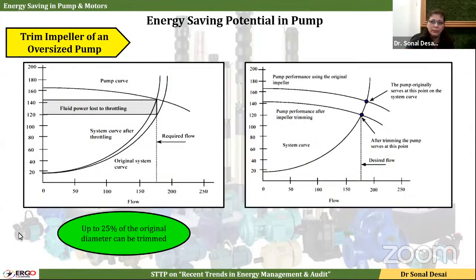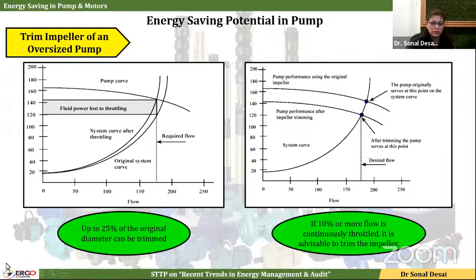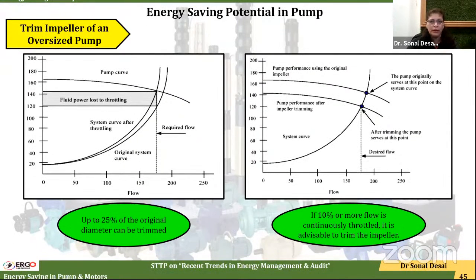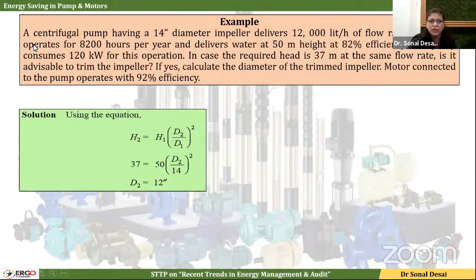Here the effect of trimming the impeller is shown. In this diagram, when we have trimmed the impeller, we make it operate over here. The initial operating condition is this, and after trimming, it is this. The thumb rule says that up to 25% of the original diameter can be trimmed. So if a 10-inch diameter impeller is there, we can make it up to 7.5 inch. And if 10% or more flow is continuously throttled, it is advisable to trim the impeller. So one more case study is given for trimming of the impeller.